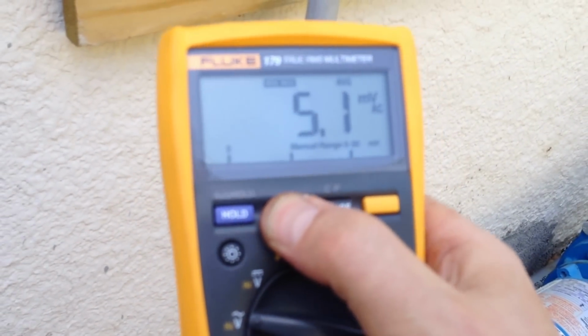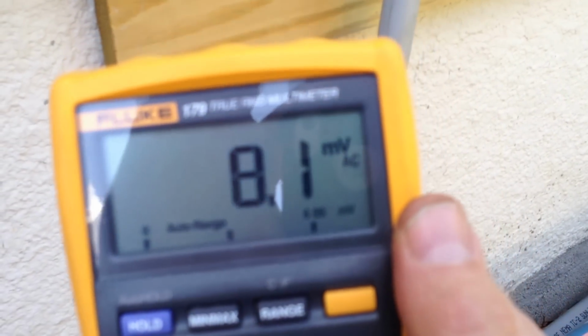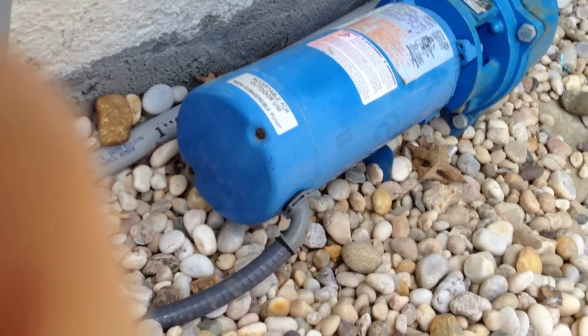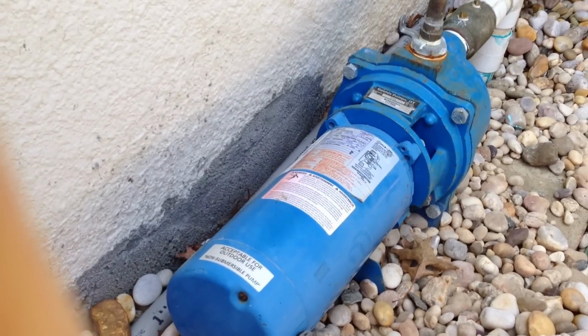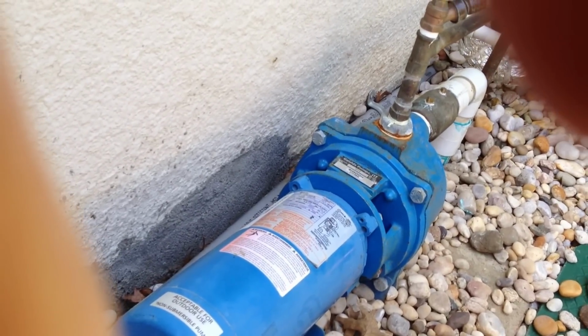Let's check out the minimum, it was 0.4, that doesn't mean anything. Let's see what it's using now. It says 8 millivolts, which is 8 amps, so it's using about 8 amps of power at 240 volts, which is about 2,000 watts. This is using 8.1 amps. The label says it generally uses 8.4 amps, so the pump is about correct, using a little less than what it says it'll use. But it's basically using about 2,000 watts at any one time, and that's a fair amount of electricity.